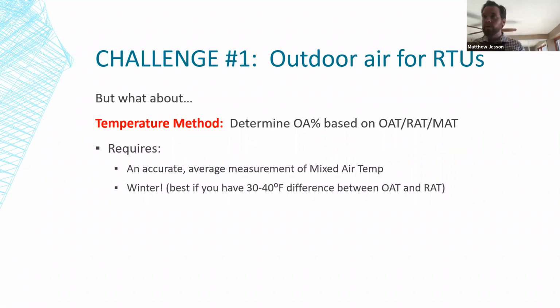And I have done that a number of times. What you need, though, is first of all, you need a good, accurate average measurement of your mixed air temp. If you take a single point temperature of mixed air, that probably will not give you a very accurate result. If you've got a good averaging sensor in there for like a DDC system, then that might work much better. The other thing you need is a big temperature difference. You can't do this when it's 75-degree return air and 70-degree outdoor air. It's just too tight of a delta T. So it's best if you've got 30 to 40 degrees of difference between outdoor air and return. So if you can control the weather, that's ideal.